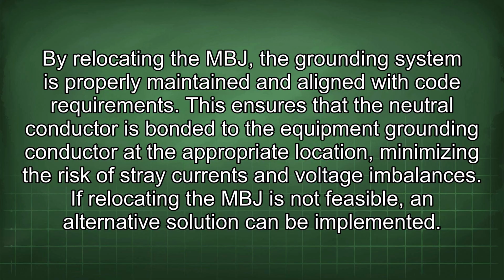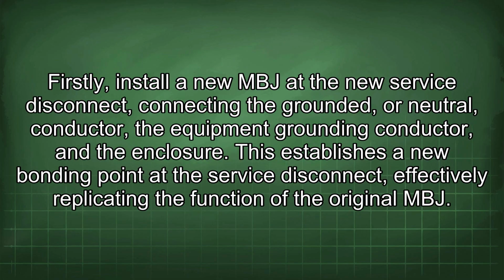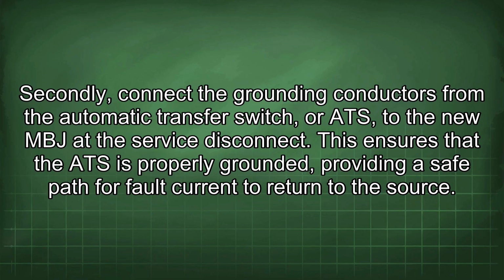If relocating the MBJ is not feasible, an alternative solution can be implemented. Firstly, install a new MBJ at the new service disconnect, connecting the grounded or neutral conductor, the equipment grounding conductor, and the enclosure. This establishes a new bonding point at the service disconnect, effectively replicating the function of the original MBJ. Secondly, connect the grounding conductors from the automatic transfer switch, or ATS, to the new MBJ at the service disconnect. This ensures that the ATS is properly grounded, providing a safe path for fault current to return to the source.